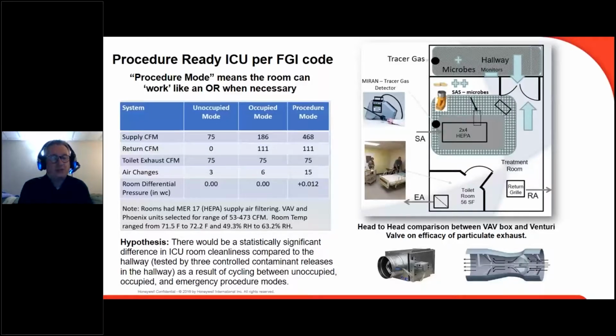And so the proposal is, what if we were able to change room states on demand? So again, if a code blue situation was to occur, we can take it from a 6 air change neutral pressure to a 15 air change positive pressure within seconds. And how does that stability affect the quality and effectiveness of that space?